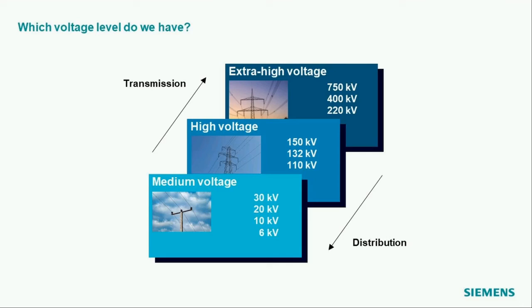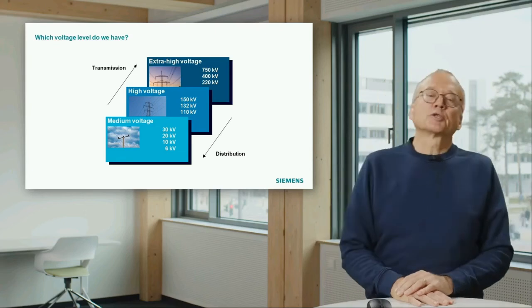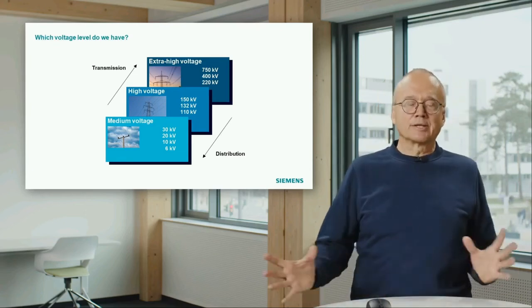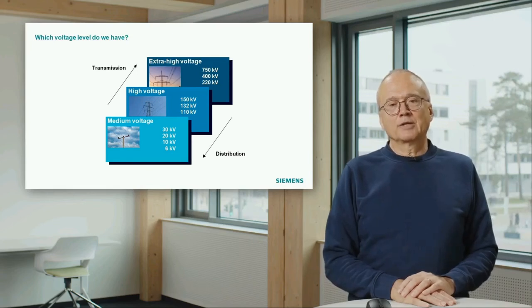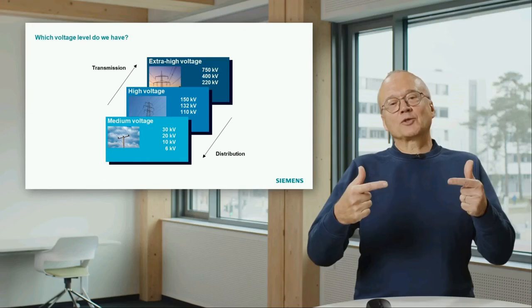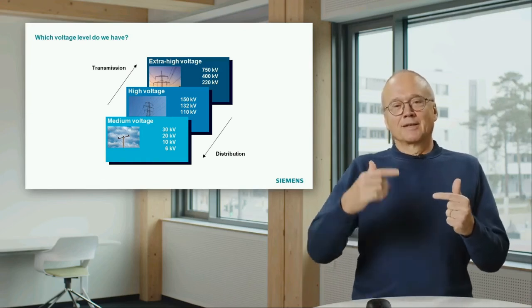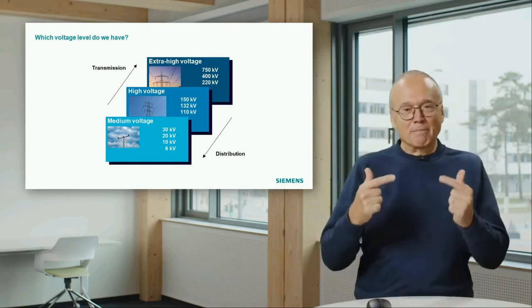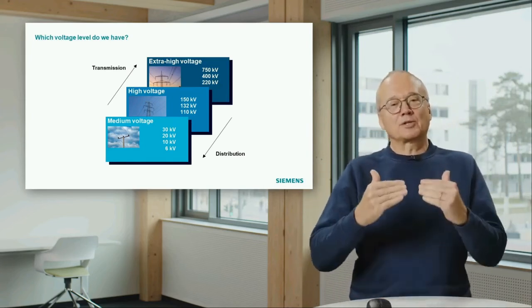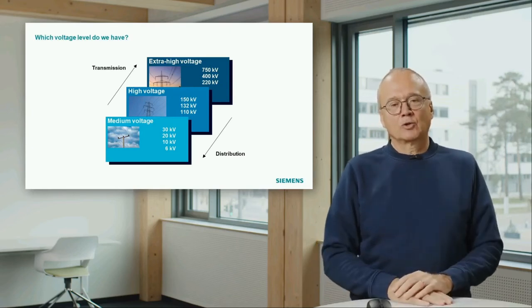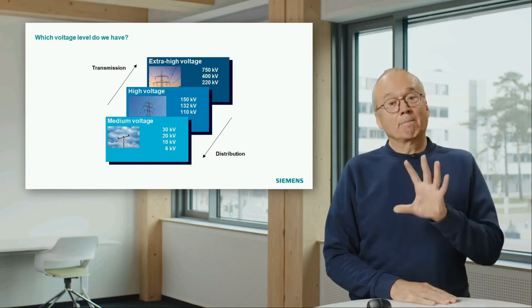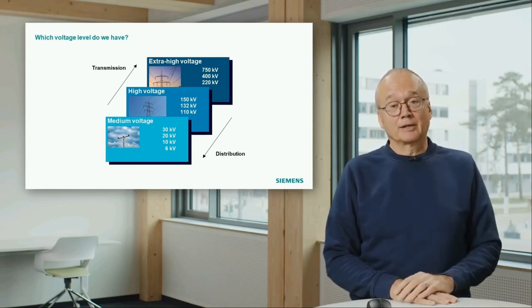It can be something between 220, 400 kilovolt, 750 kilovolt, or trials are already done with even higher voltages. The voltage level which is used depends on the size of the country, the distances, and the amount of energy we have to transport. Always remember, for the protection relay, the voltage level doesn't make a big difference because the voltage is always transformed down to that level which is seen by the relay. But the concepts to do protection are different in high voltage level compared with medium voltage.